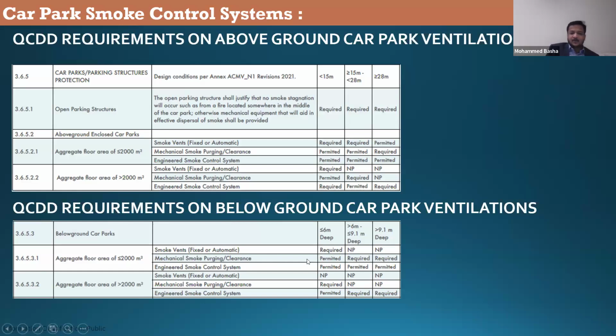You can have a mechanical smoke purging, permitted. Engineered smoke control is permitted. I am not telling you should not use a jet fan system, but you have a cheaper option, a smoke vent system also. If the aggregate floor area is greater than 2000 square meter, then yes, we have to make the mechanical smoke control system. We cannot rely on smoke vents. Here you need a full engineered control system. Permitted, required.